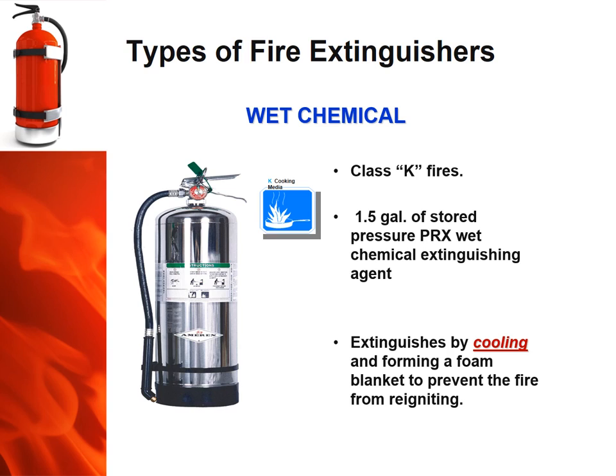The last extinguisher discussed today is used for class K fires — a relatively new extinguisher used in commercial kitchens. It contains 1.5 gallons of stored pressurized PRX wet chemical agent, with a discharge time of about 40 seconds and a maximum effective range of about 10 to 12 feet. It fights fires by cooling and forming a foam blanket to prevent reignition.